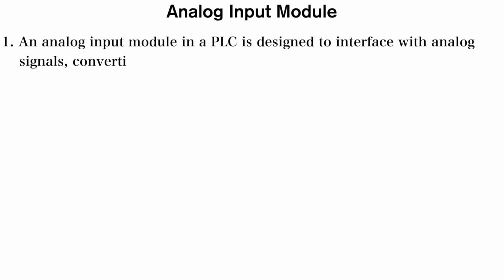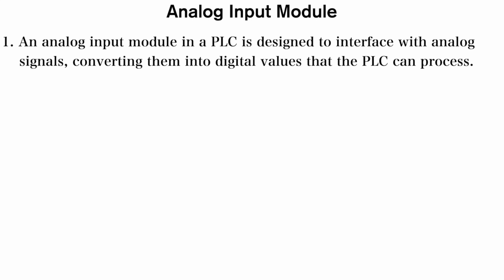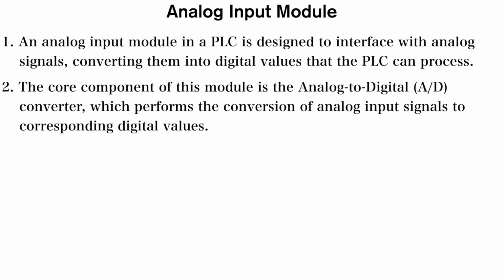Now comes the analog input module. An analog input module in a programmable logic controller is designed to interface with analog signals. First, it converts them into digital values that the PLC can process. The core component of this analog input module is the analog to digital converter, commonly known as the ADC or the A/D converter. This A/D converter performs a conversion of analog input signals to the corresponding digital values or variables.